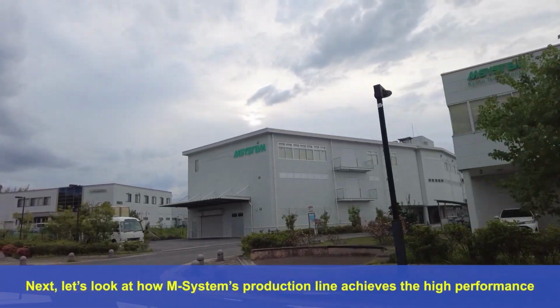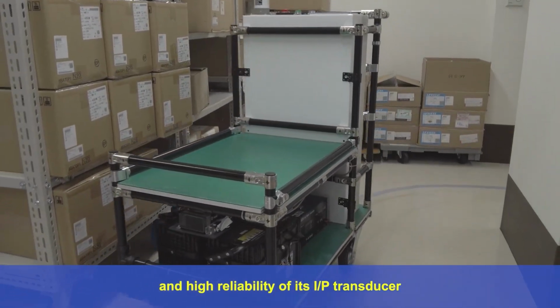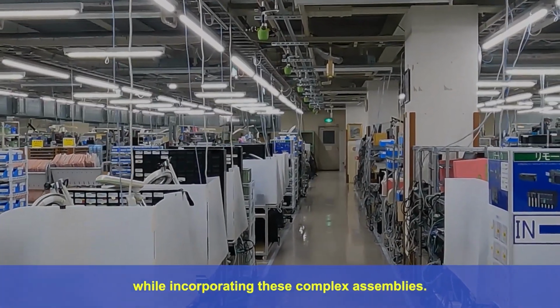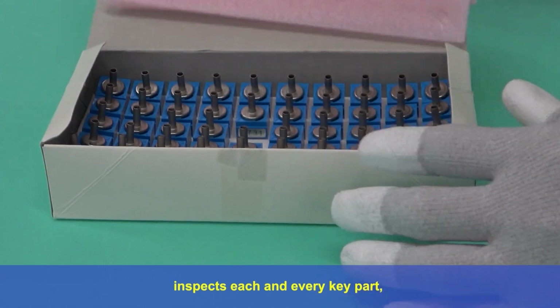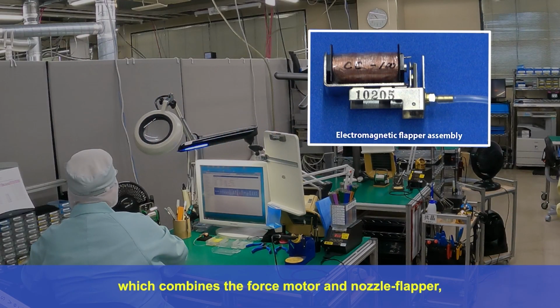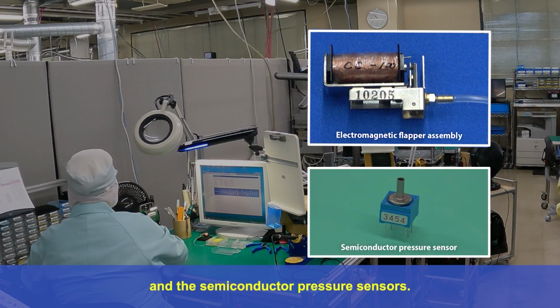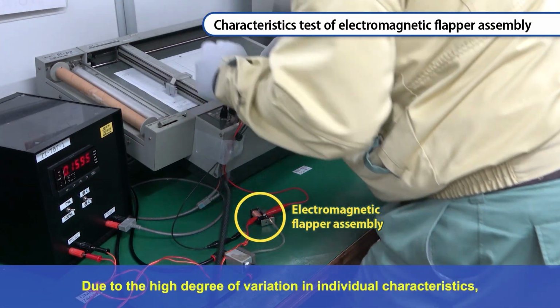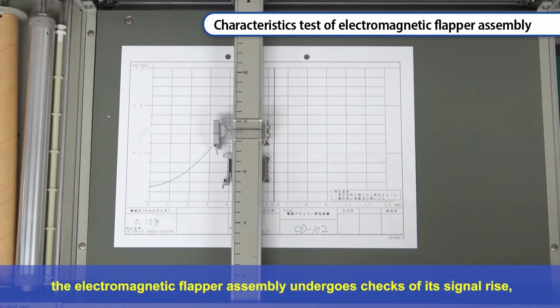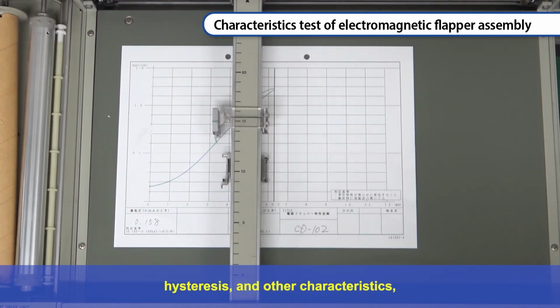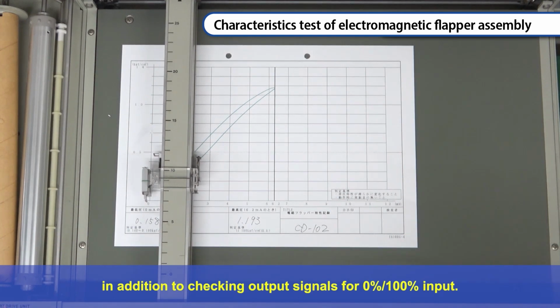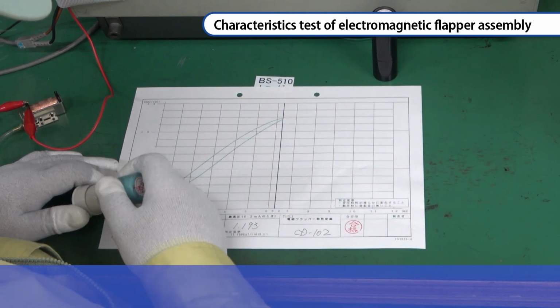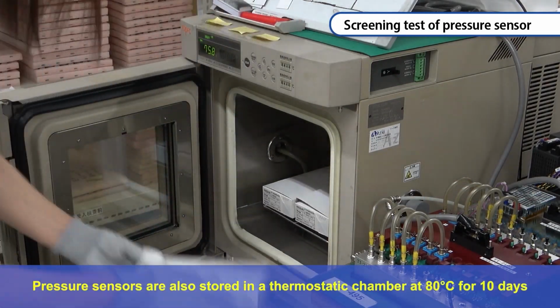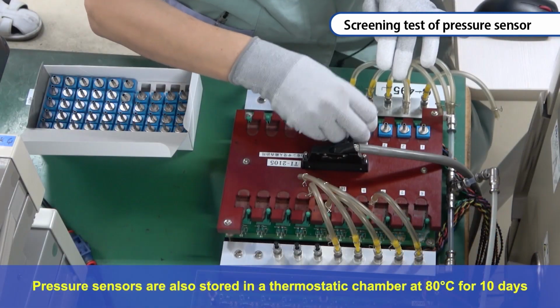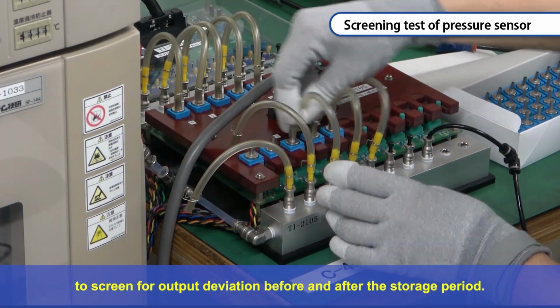Next, let's look at how M-System's production line achieves the high performance and high reliability of its I-to-P transducer while incorporating these complex assemblies. The purchasing and production section inspects each and every key part, such as the electromagnetic flapper assemblies, which combine the force motor and nozzle flapper, and the semiconductor pressure sensors. Due to the high degree of variation in individual characteristics, the electromagnetic flapper assembly undergoes checks of its signal rise, hysteresis, and other characteristics, in addition to checking output signals for 0% and 100% input. Pressure sensors are also stored in a thermostatic chamber at 80 degrees Celsius for 10 days to screen for output deviation before and after the storage period.